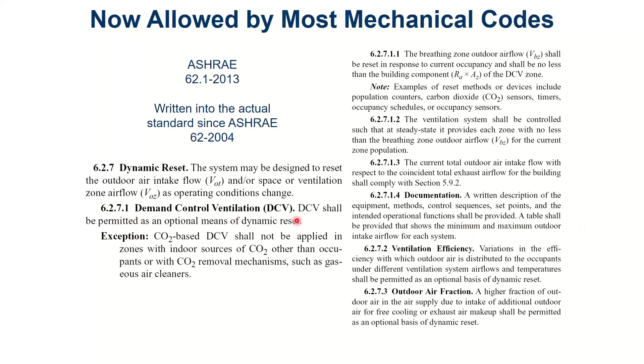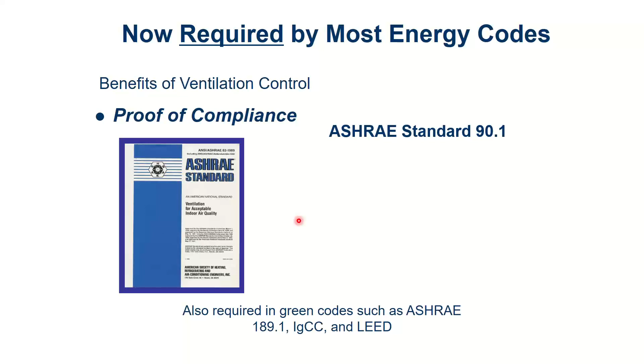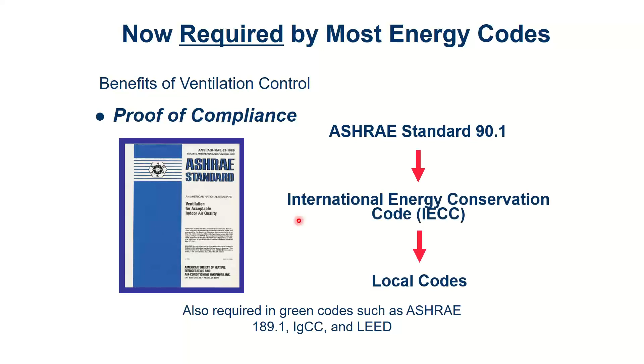The energy codes not only allow it, but actually require it now. It's not even an optional thing. All of the energy codes have a requirement for every area that has an energy code—I think 38 states have an energy code at this point—and all of them require demand control ventilation. Not for every single space, just for the densely occupied spaces.